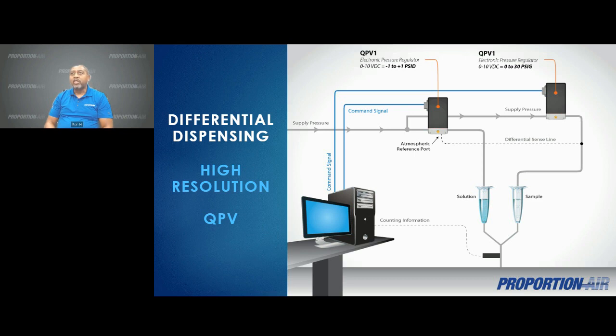The QPV controlling pressure over the sample is calibrated 0 to 30 psi. The QPV controlling pressure over the solution is calibrated -1 to +1 psi, with the intention of constantly maintaining a specific differential pressure of solution to sample. The QPVs come standard with an atmospheric reference point. This is the 0 point where pressure is referenced. The solution dispensing QPV has its atmospheric reference point port tied to the output of the sample dispensing QPV. That is shown as the differential sense line. This means that whatever pressure is being controlled by the sample dispensing QPV, the solution dispensing QPV will use this as its baseline for controlling pressure. For example, if the QPV1 controlling the sample is set at 15 psi, the QPV1 controlling the solution would be plus or minus 1 psi or 14 to 16 psi. That controls the amount of solution that goes into the sample.